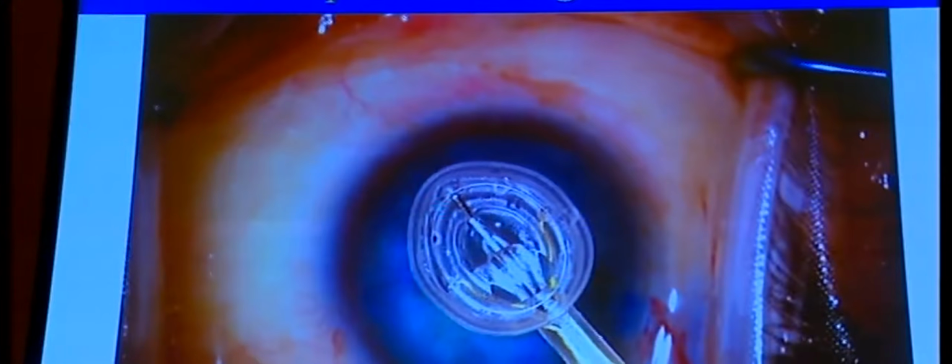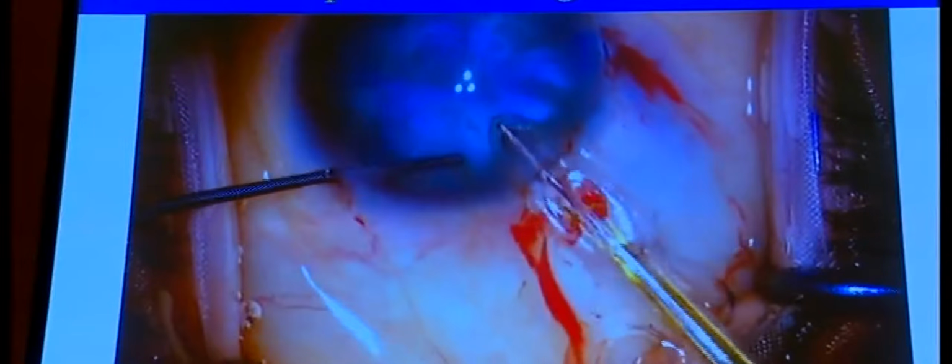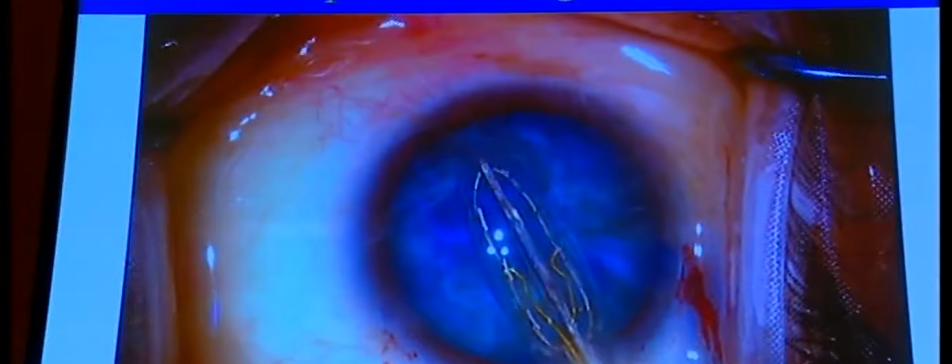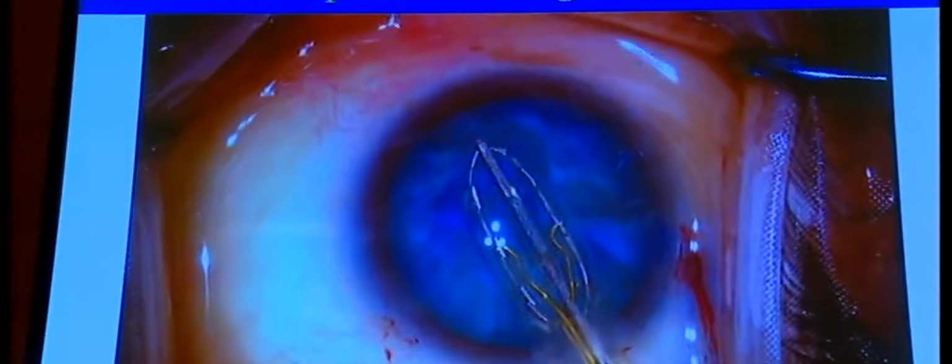And this is the Zepto on the underside. There's a cusp, and you see this metal ring. This is called the nitinol ring. The property of the nitinol ring is that it has an excellent memory. So you can stretch it, it goes into the eye, and when you pull back the plunger, it comes back to its original shape.